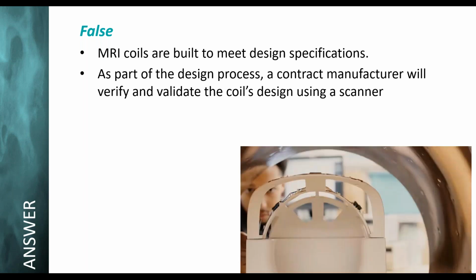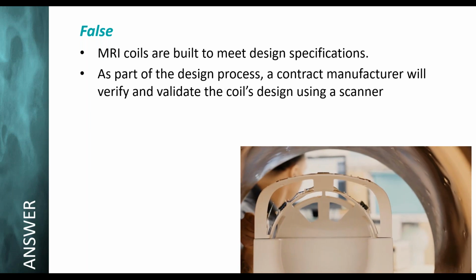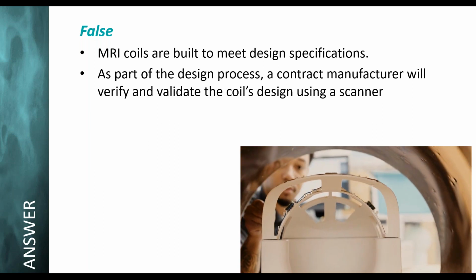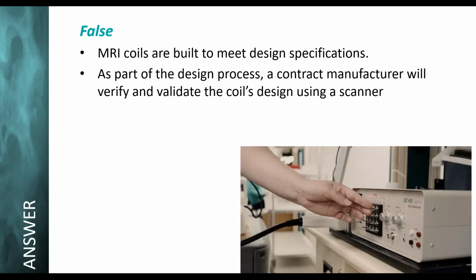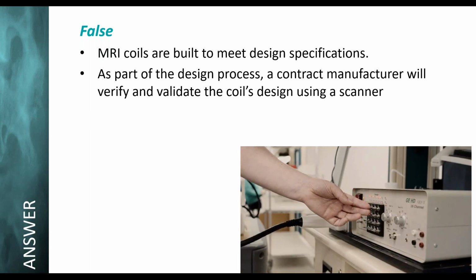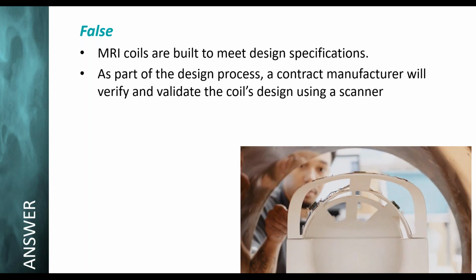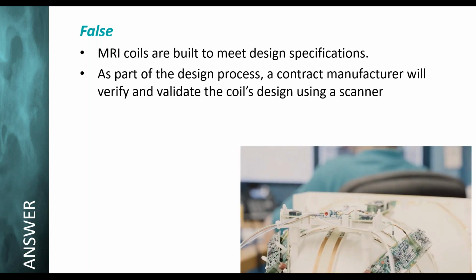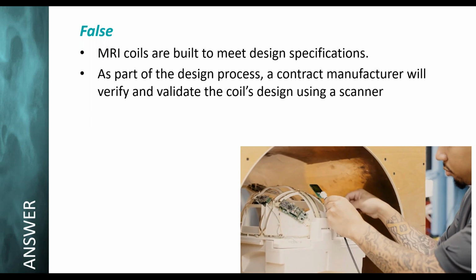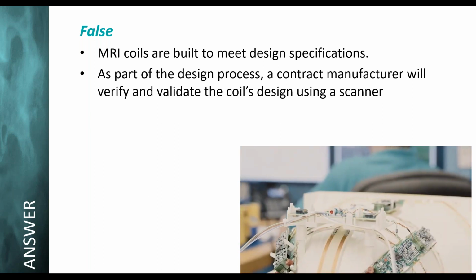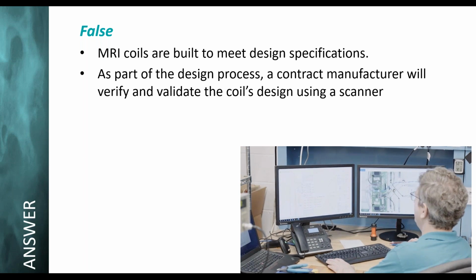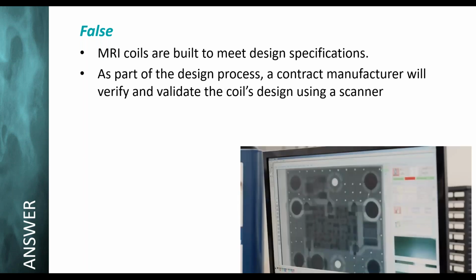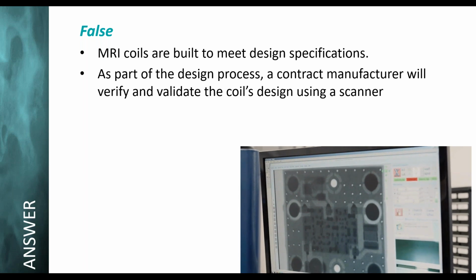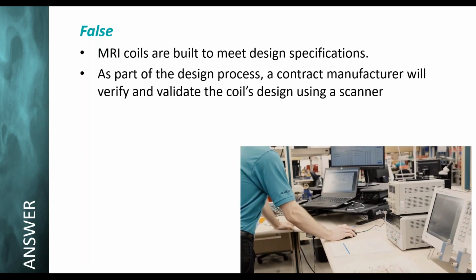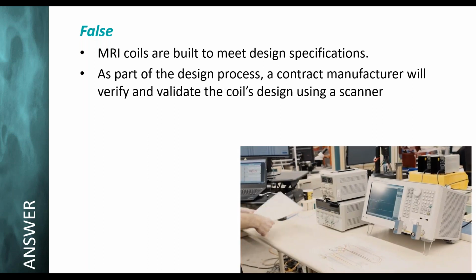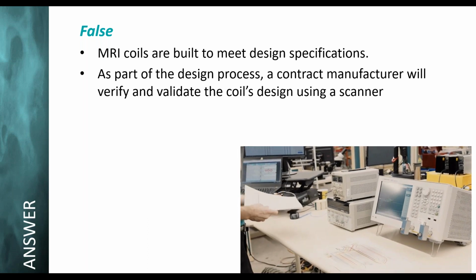There is nobody on this planet that does coil repair that has the resources to buy a test bed for every single coil they repair. You can't do it. It's cost prohibitive. I mean, I mentioned, you're paying $2 to $3 grand for a coil repair. An MRI system costs $1 million too. And we do over 1,100 different coils. So if we were to have a test bed, we'd have to have 200-300 test beds. And so our return on our investment would be sometime around when my grandchildren's grandchildren are retired.